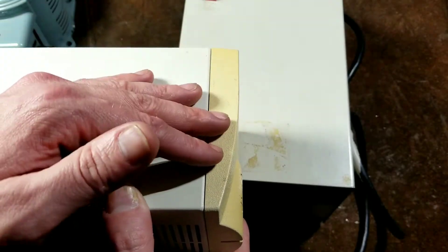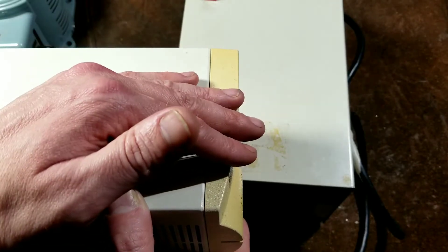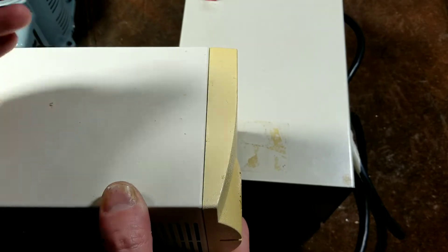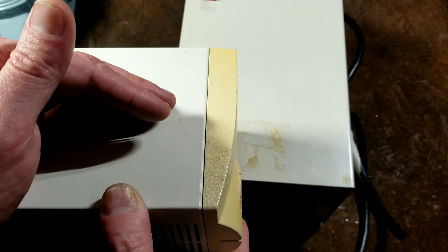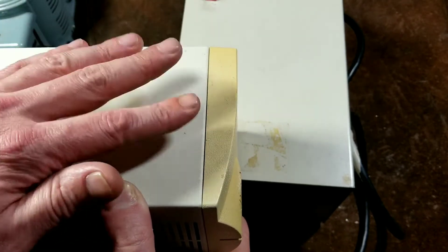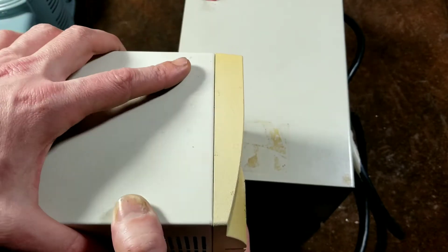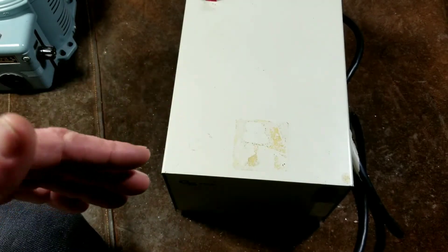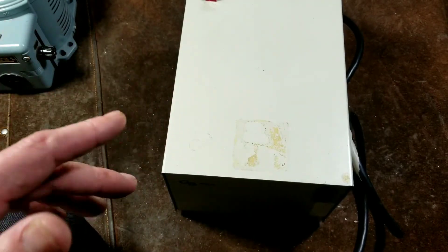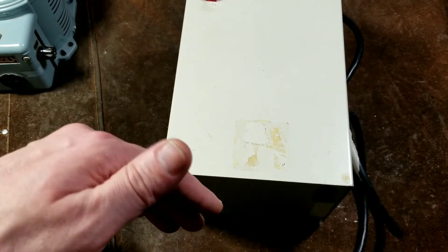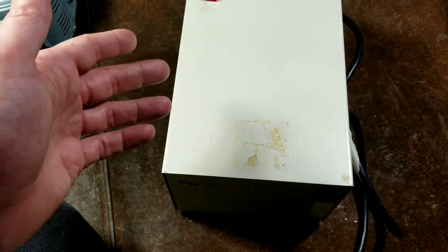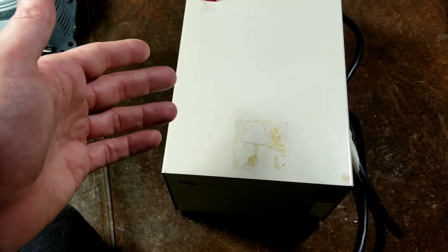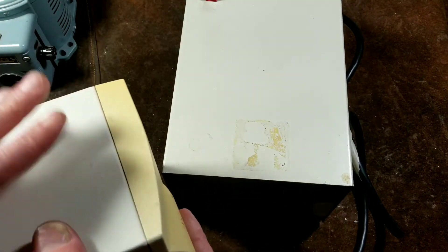When it comes to power conditioning, you have three transformer-based options. An isolation transformer, which is super high quality filtering but can't do anything if you have a brownout or something on your power line. The other two units use different forms of transformers to help not only provide power filtering, although the filtering isn't as good as an isolation transformer.